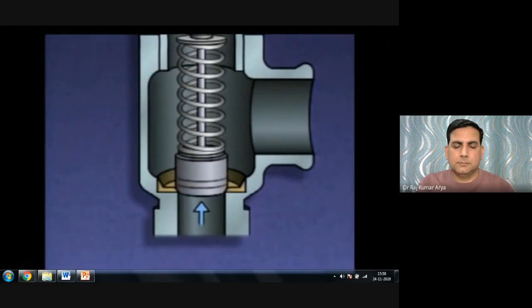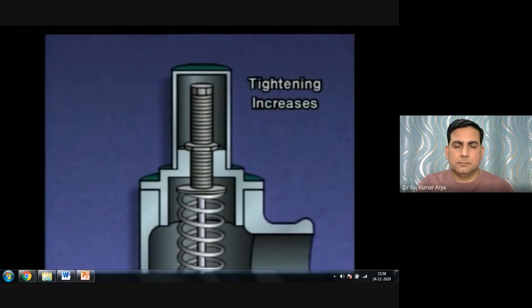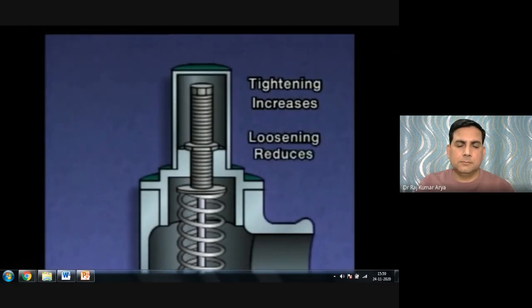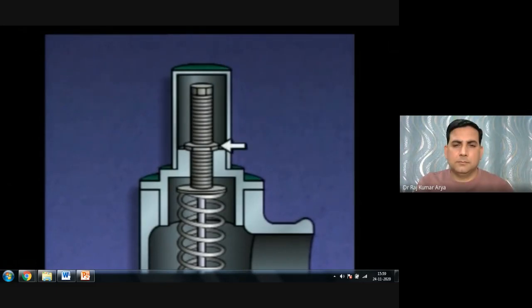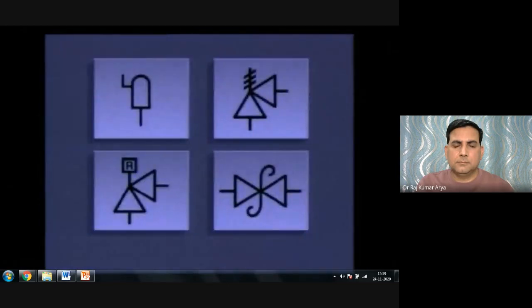The adjusting screw is used to change the force exerted by the spring. Tightening it increases the force on the disc, raising the pressure setting at which the valve opens. Loosening it reduces the force on the disc and allows the valve to open at a lower pressure. The lock nut holds the adjusting screw in position after the spring force has been set, and the assembly is usually covered by a cap. On a piping system diagram, a relief valve can be represented by various symbols, often with the relief valve setting included beside the symbol.